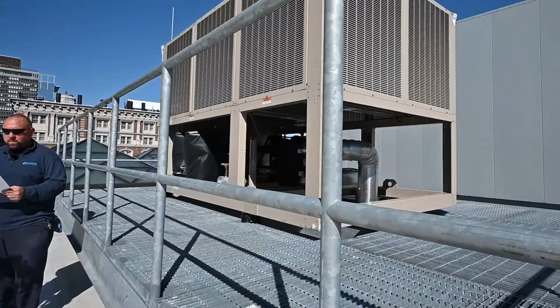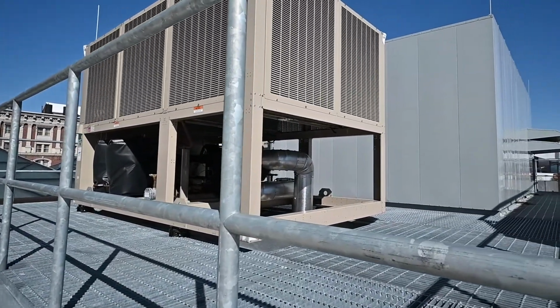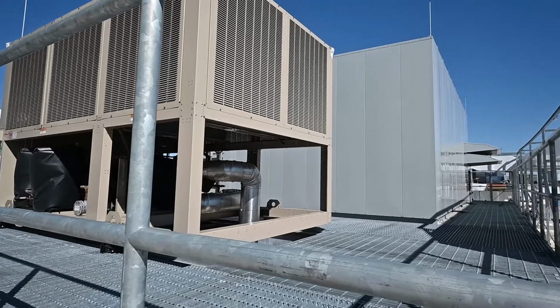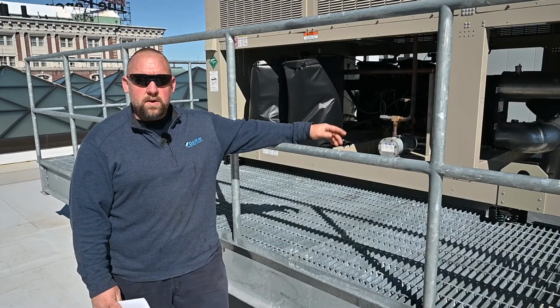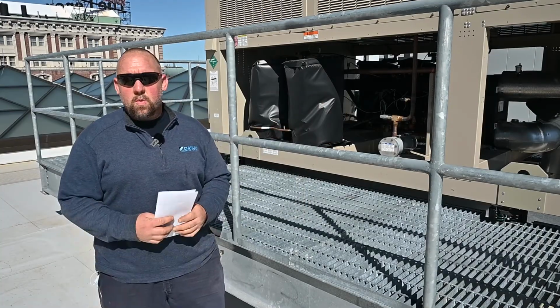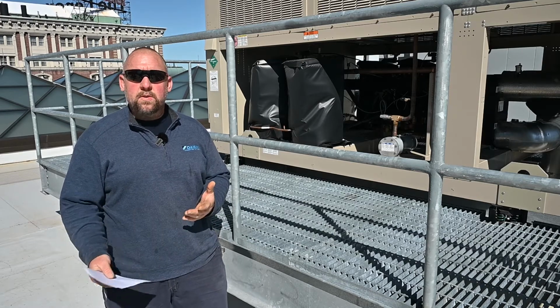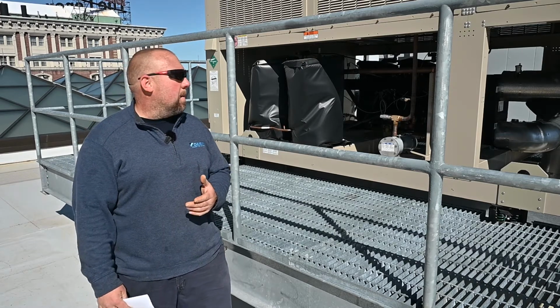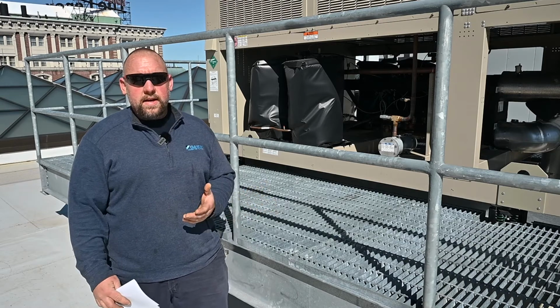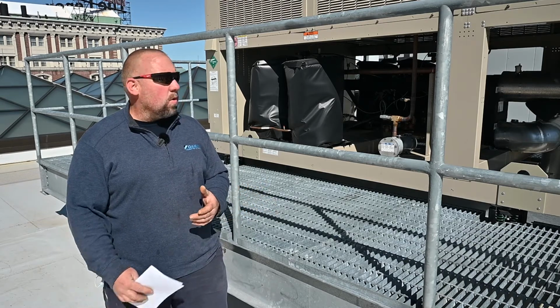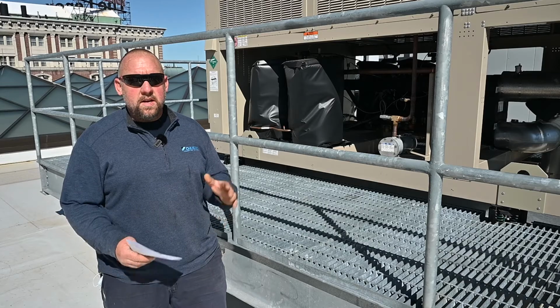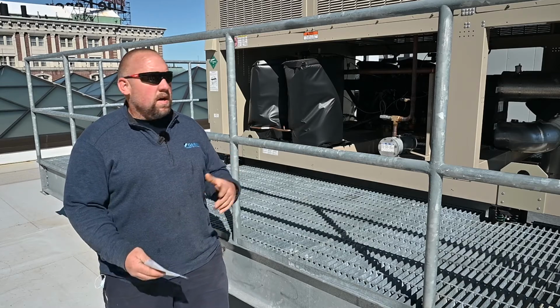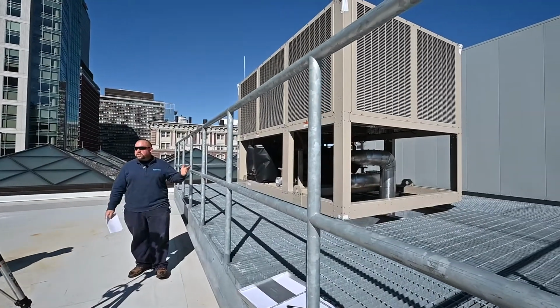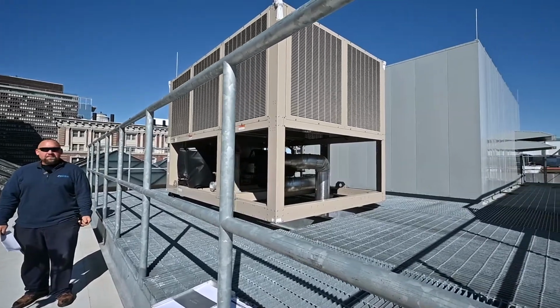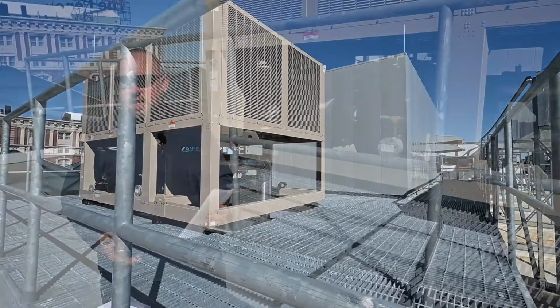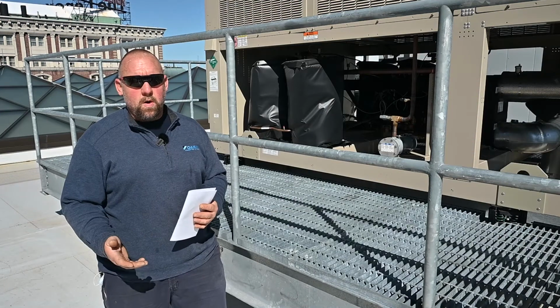You can see if you go underneath, they almost look like radiator coils. They're a newer style coil. They're aluminum. There's no recommendation for actual chemicals to be used on them. Water is really the best thing. Any of the older chillers or older equipment you may have seen have very thick coils. These are very thin, just like I said, similar to the radiators in your cars. They can be blown out pretty easily with just water pressure from a water hose.